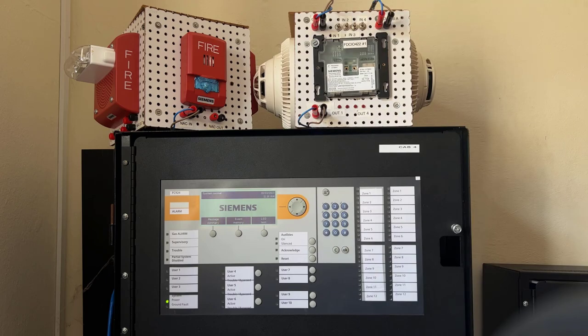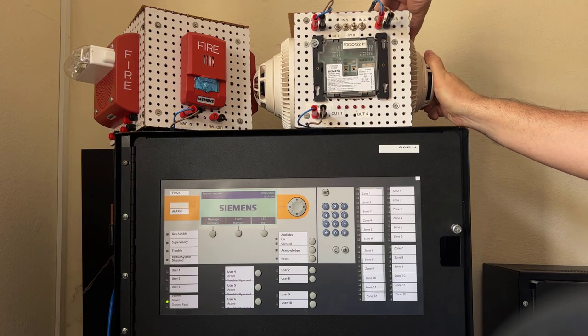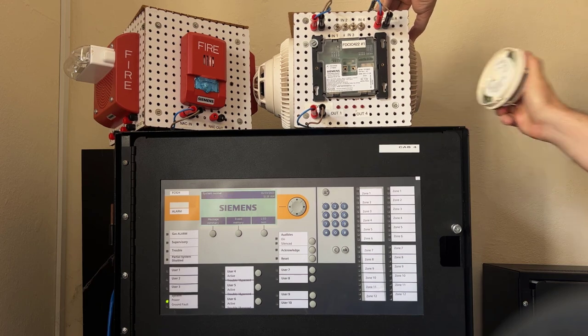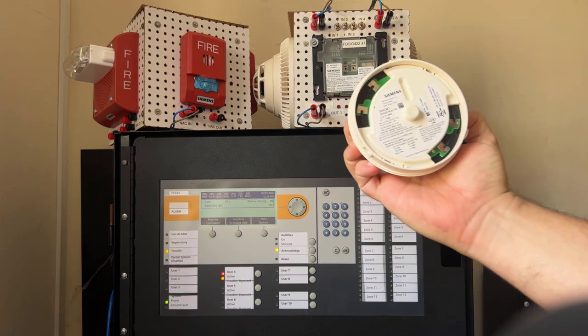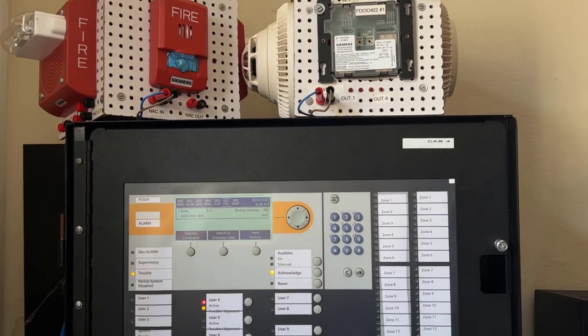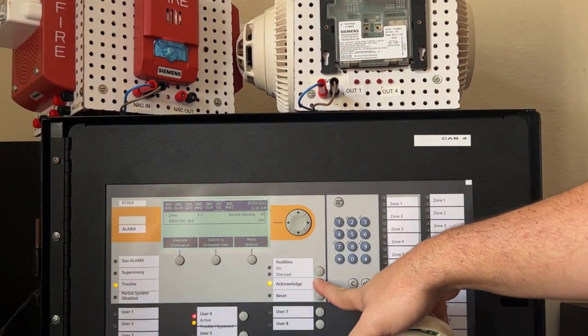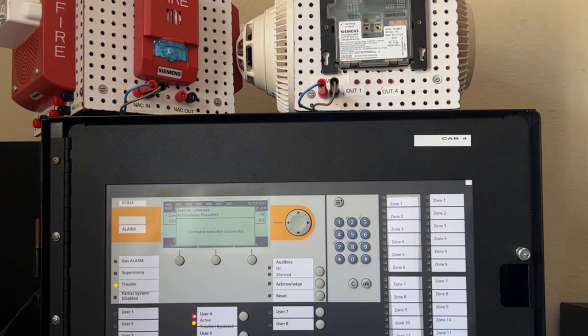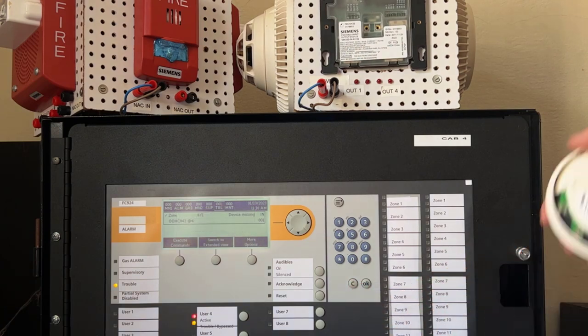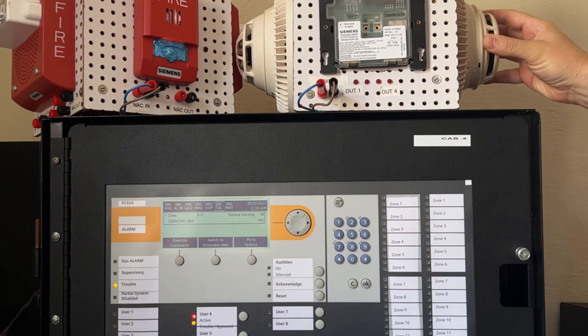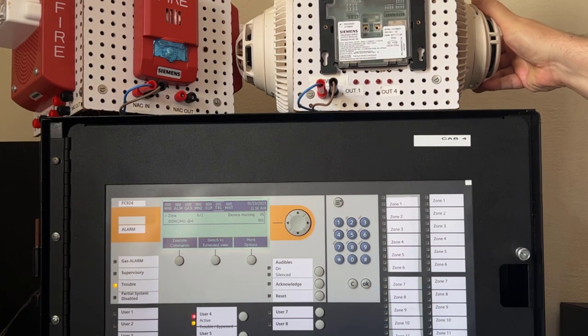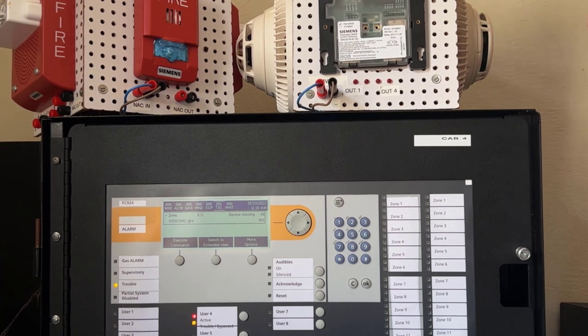Next, I created a device missing condition on the loop, and it is very straightforward. Upon reinstalling the missing device, the system goes back to a normal condition.